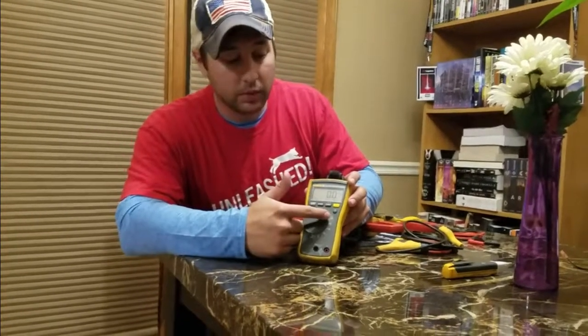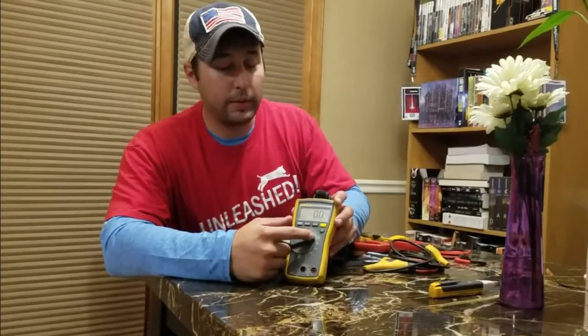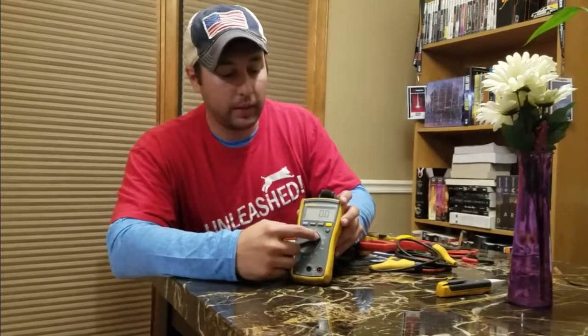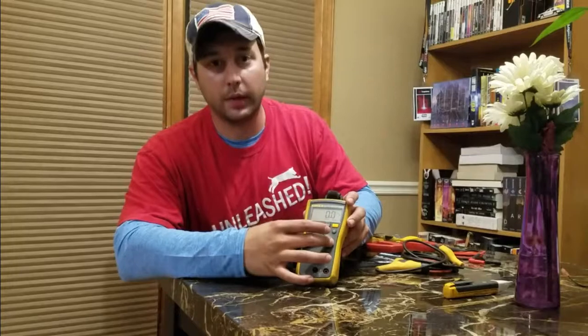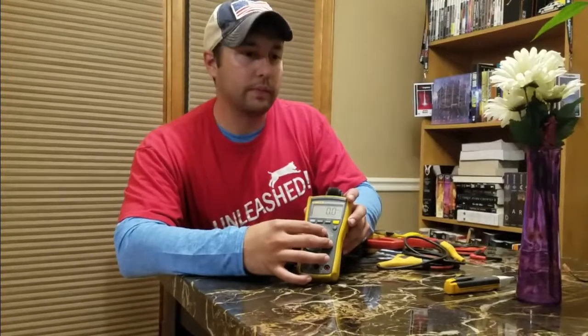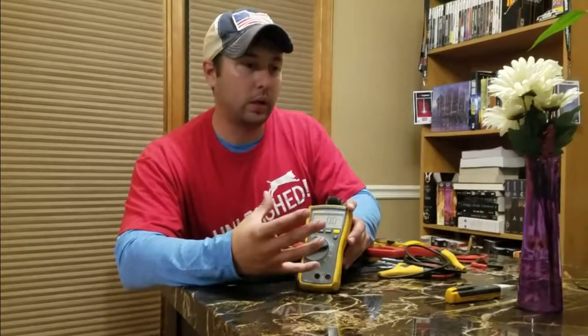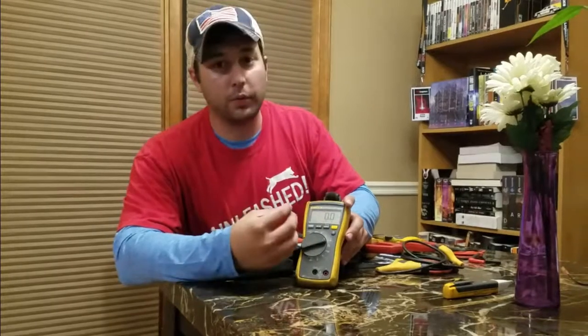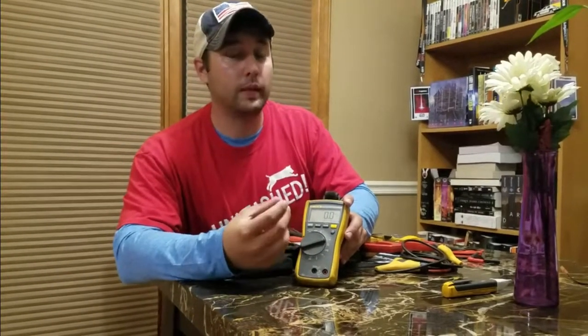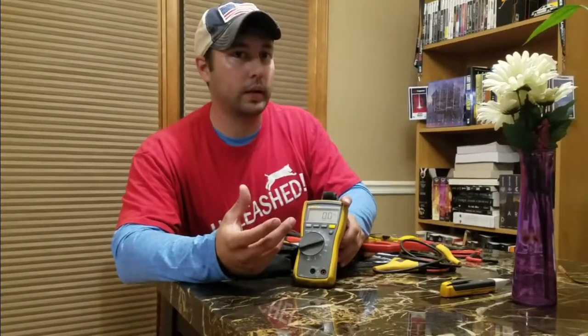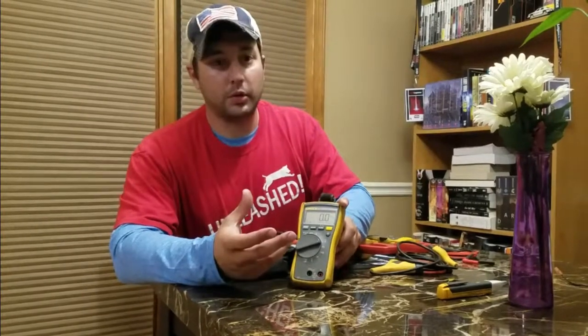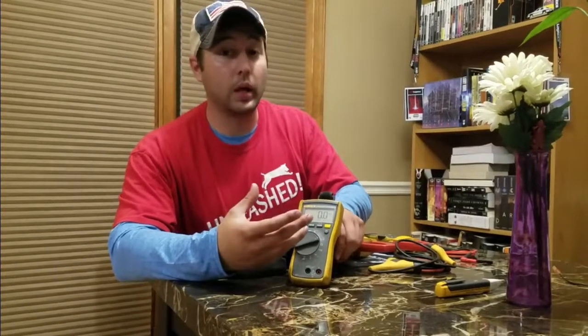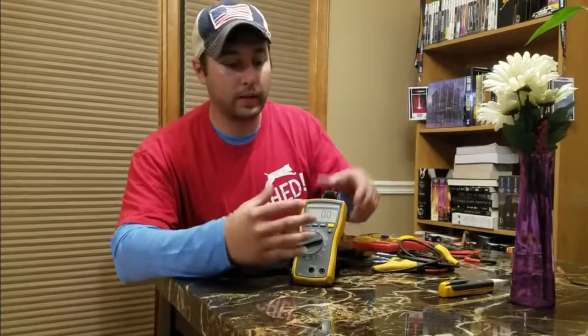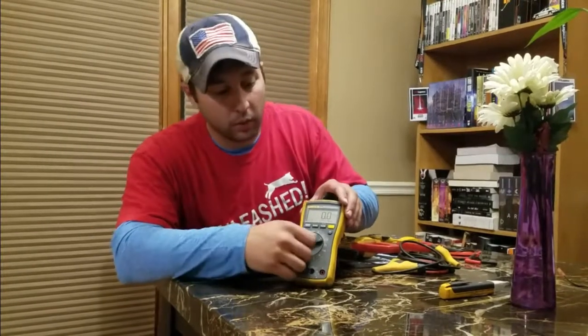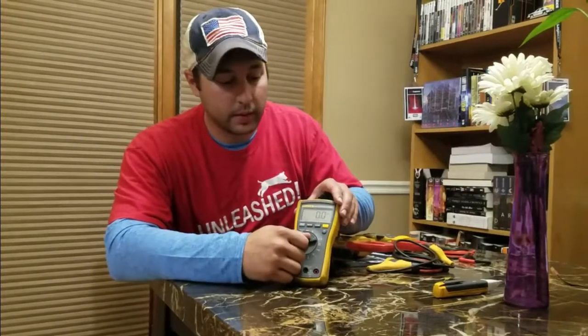This one has microamps. You're probably not going to use that, I'll be honest. I use it for flame rectification. Boilers and furnaces send power through a flame to prove it has lit, as a safety feature confirming the gas did light. If the gas didn't light and there's no flame, there won't be an electrical path. So again, that's not really necessary for most people.